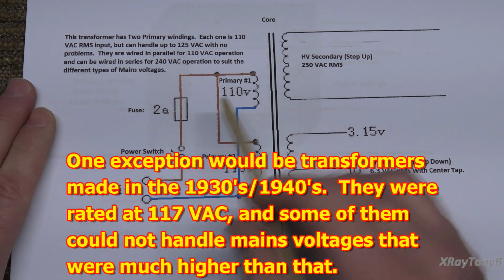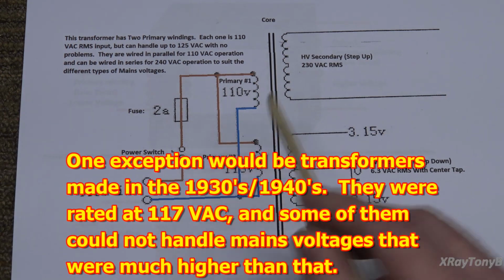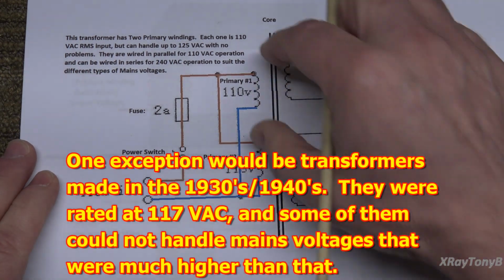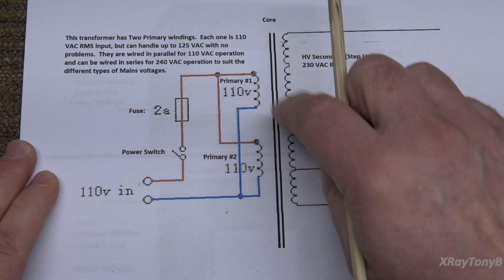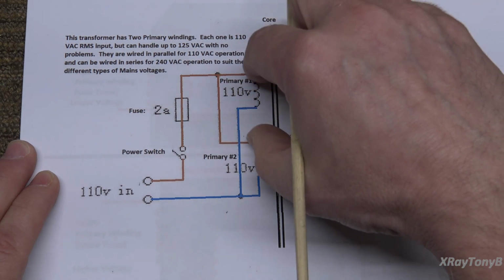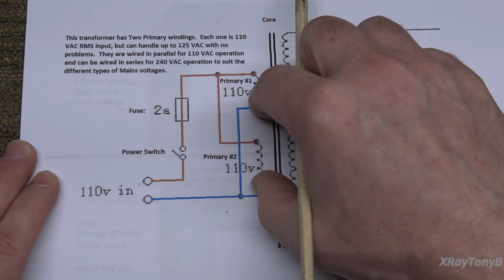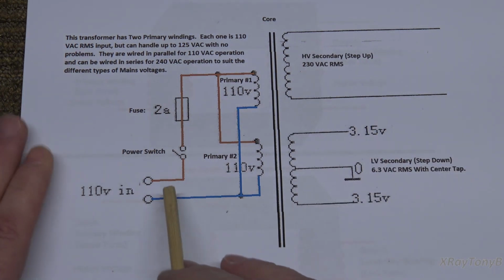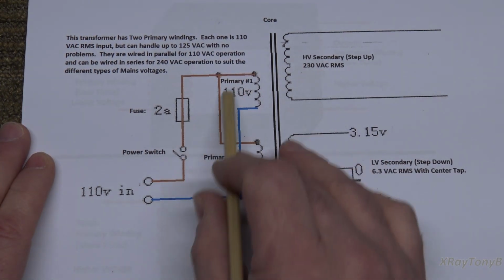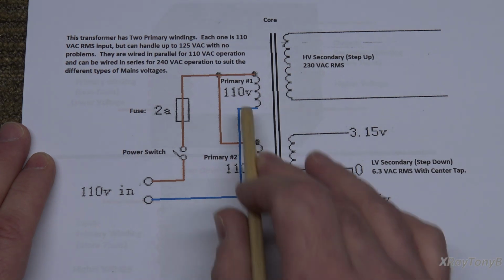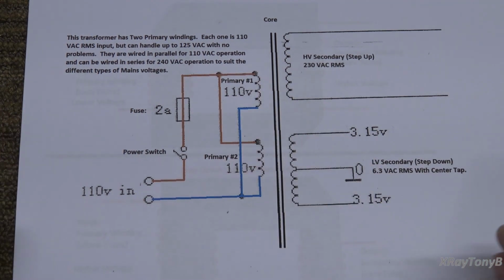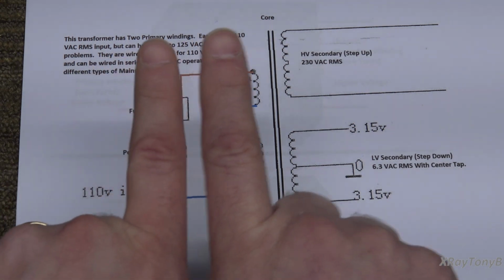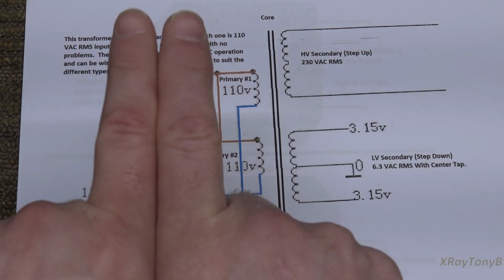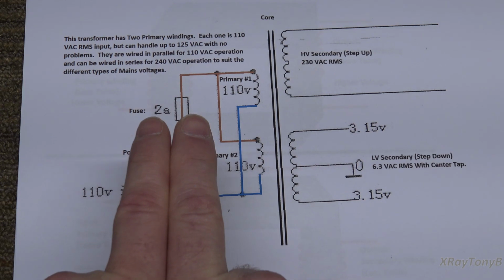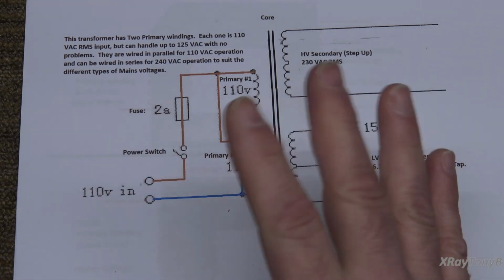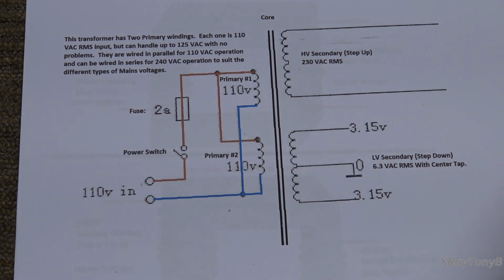The cool thing about this transformer is we can wire it this way. You see these two are wired in parallel, so the two tops of these windings are connected together and the two bottoms are connected together. Each one can take that 120 volts or 110 volts, and since they're wired in parallel, the two wires double up, so you can handle twice the amount of current. That's going to be important in a minute, and we'll find out why later in this video.